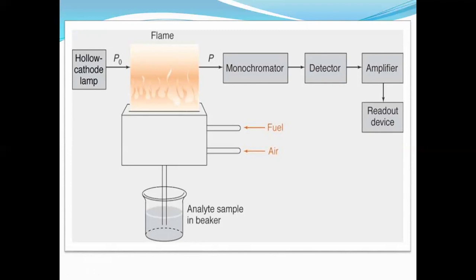Some instruments consist of a chopper. The next component is the monochromator, which is used for the separation or filtration of polychromatic light — it converts polychromatic light into useful monochromatic light. Then there is a detector which detects the absorption of light, followed by an amplifier and readout device.